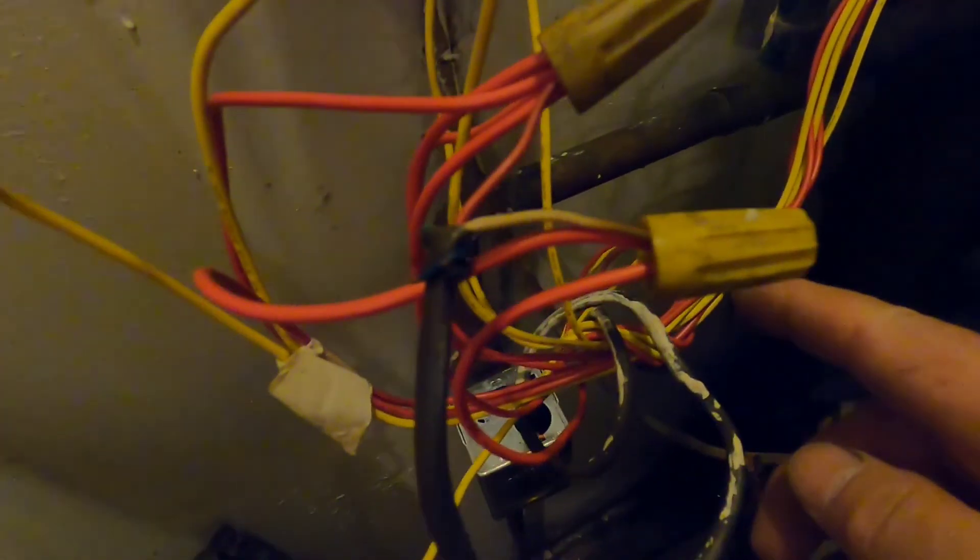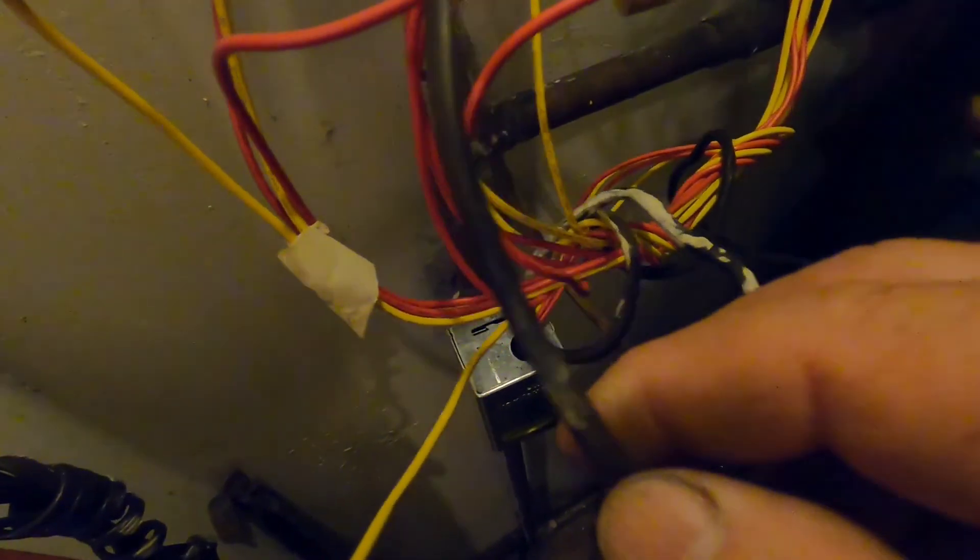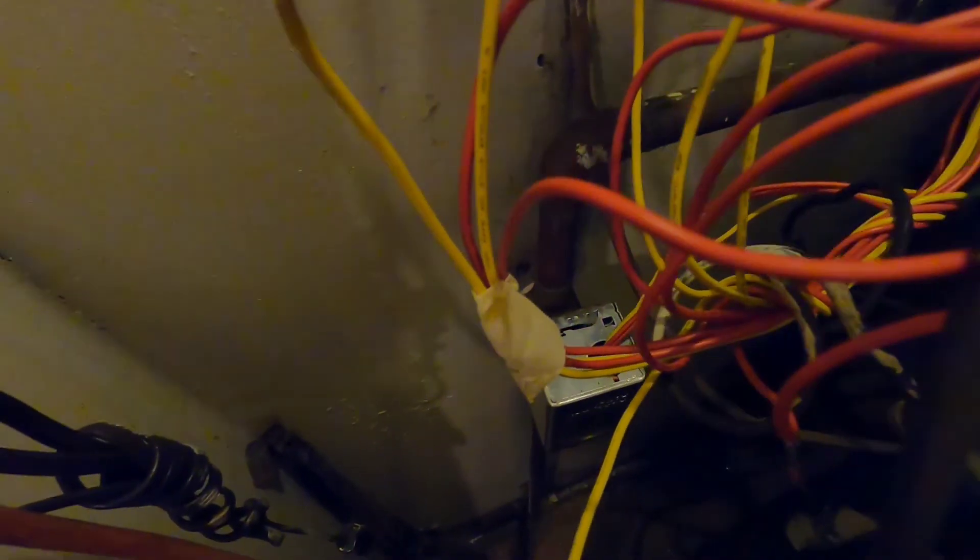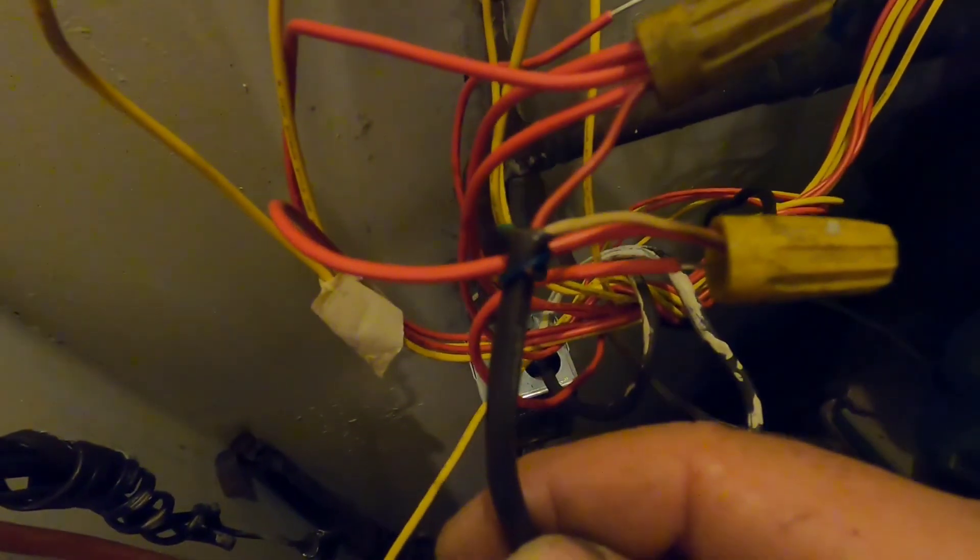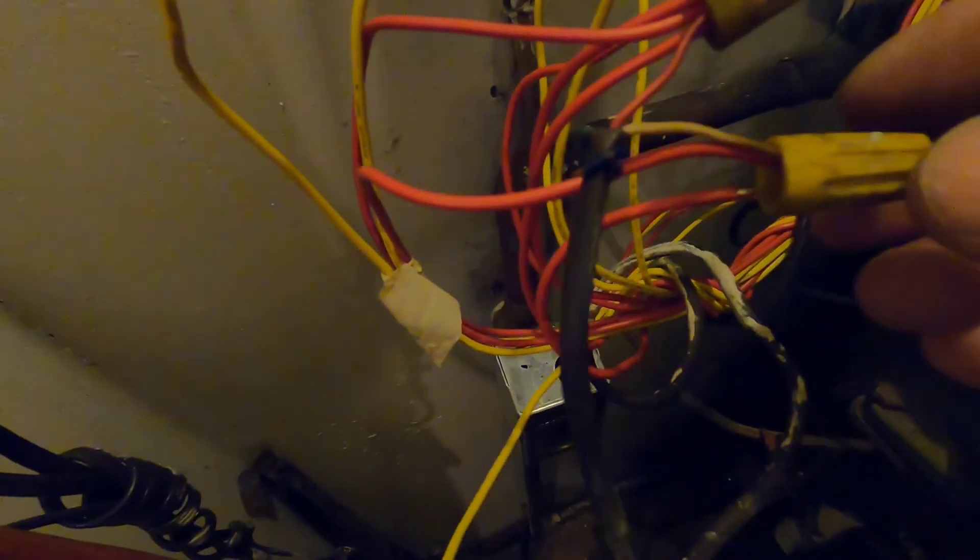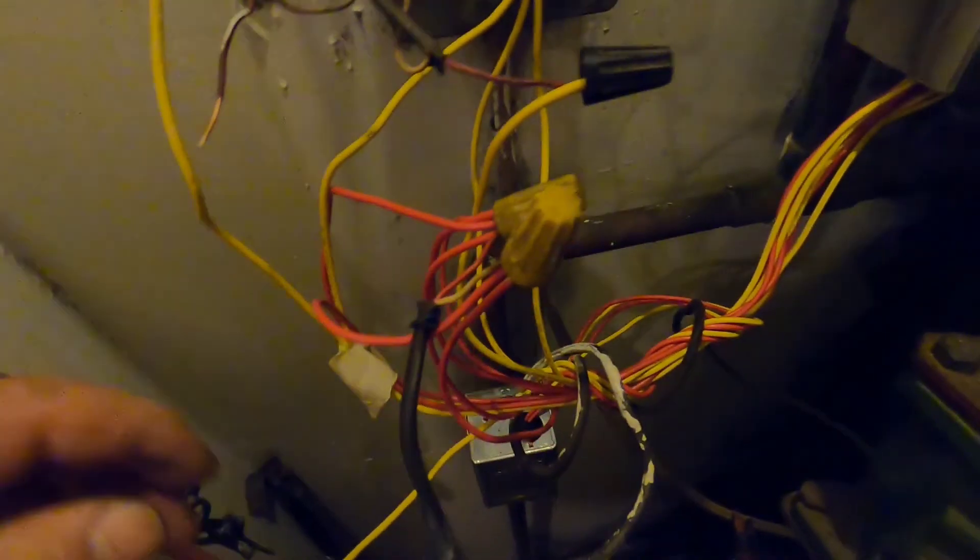From the switch, you have two wires coming out from the switch, and they get connected to the wire that goes back to the aquastat. And in this case, we have three. So again, three wires are connected to the two wires from the aquastat. Three on one leg, three on the other leg. This wire has to be connected. And that's it.